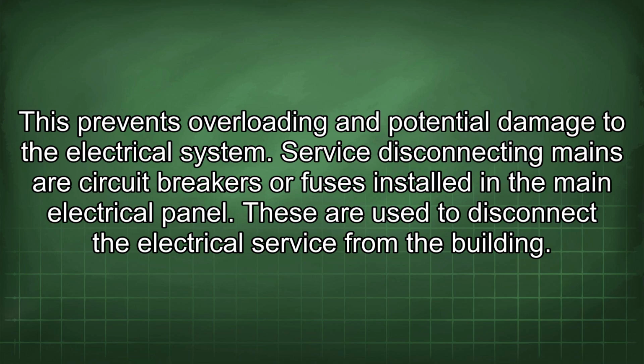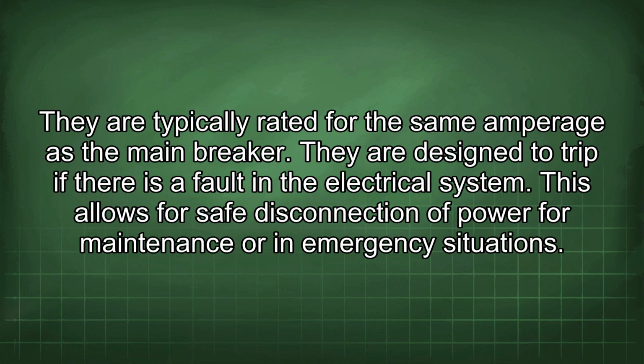Service disconnecting mains are circuit breakers or fuses installed in the main electrical panel. These are used to disconnect the electrical service from the building. They are typically rated for the same amperage as the main breaker. They are designed to trip if there is a fault in the electrical system. This allows for safe disconnection of power for maintenance or in emergency situations.